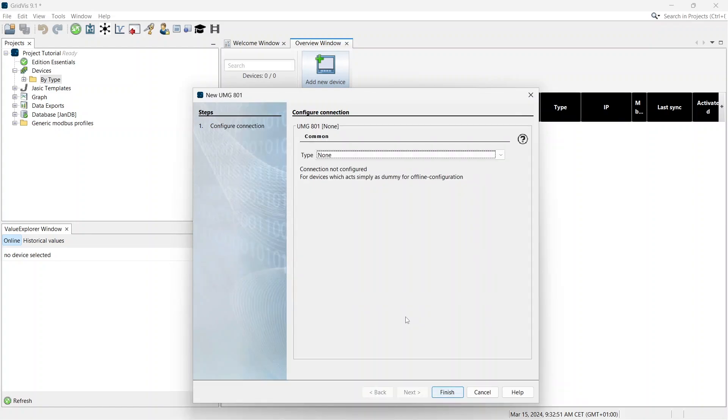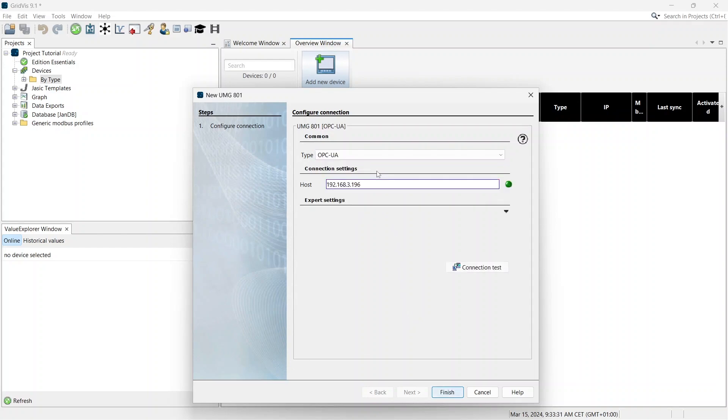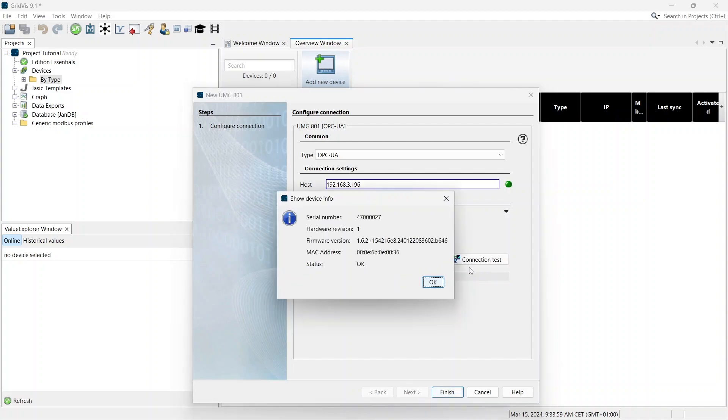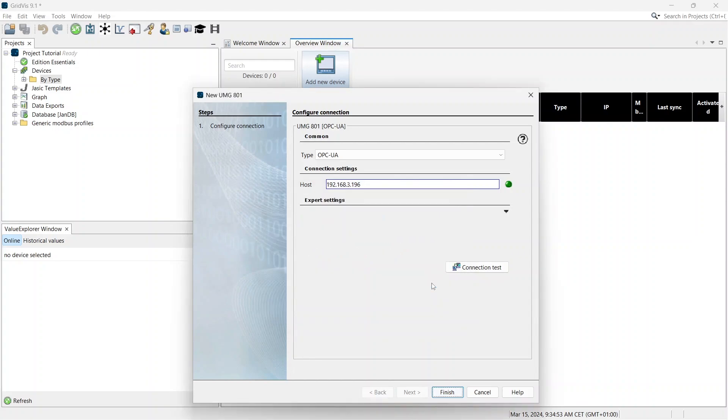In the next step, select the connection type to add your device. The UMG801 is added via OPC UA. You can find out how to locate the IP address in your device in the user manual. Click on Connection Test to check the IP address. The result of the connection test is displayed in a pop-up window. Click on Finish to add the device to your project.